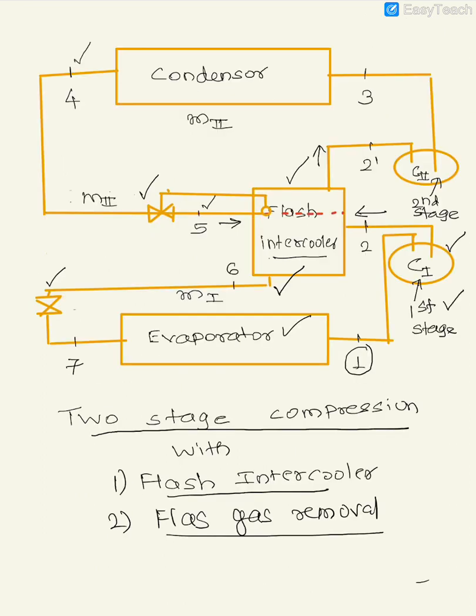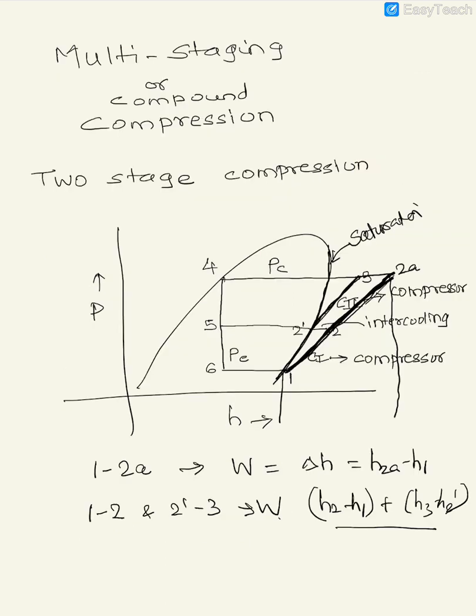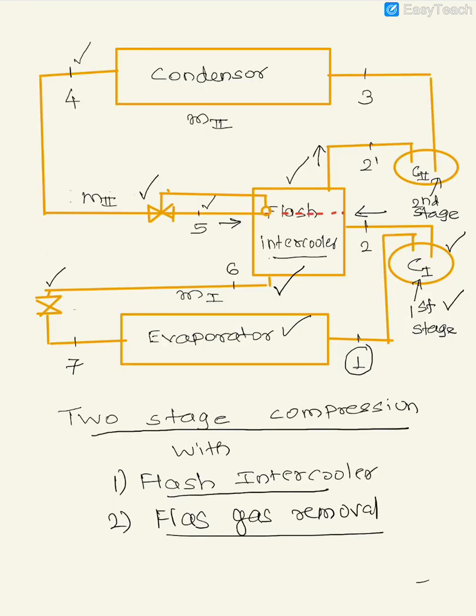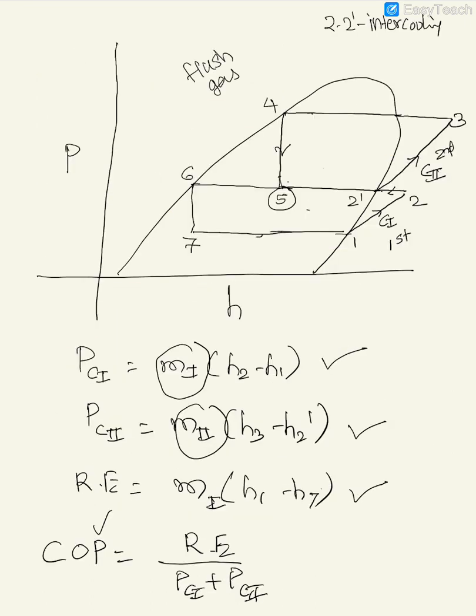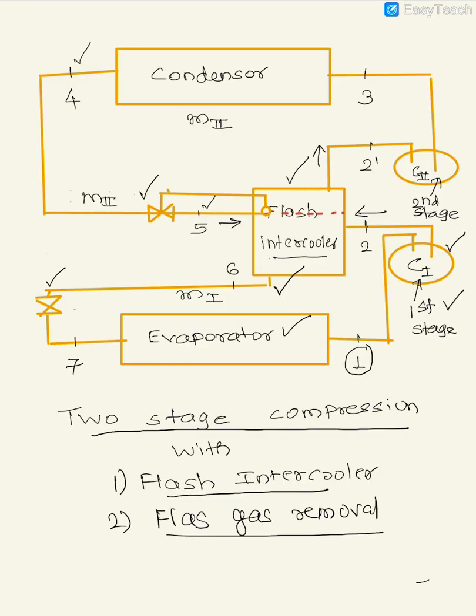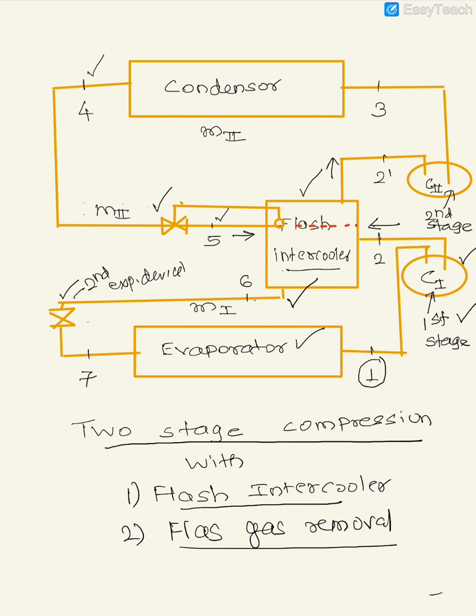From state 5 to 6, the flash gases are removed, and the refrigerant enters the second throttling device at state 6. This is the second expansion device, and you see that the entry to this second throttling device is a saturated liquid. So at state 6, the flash gases have been removed because of the flash intercooler, and those flash gases have gone to compressor 2.